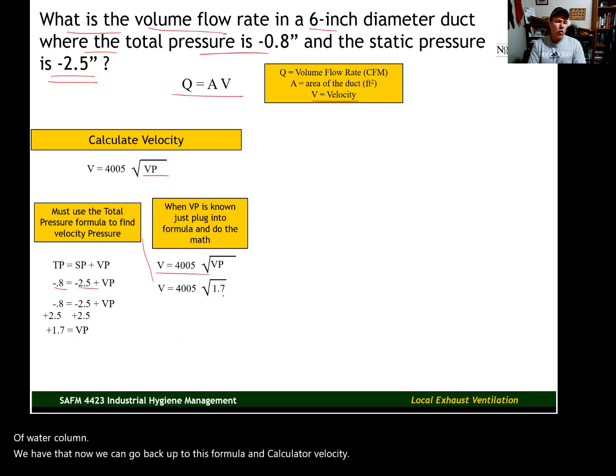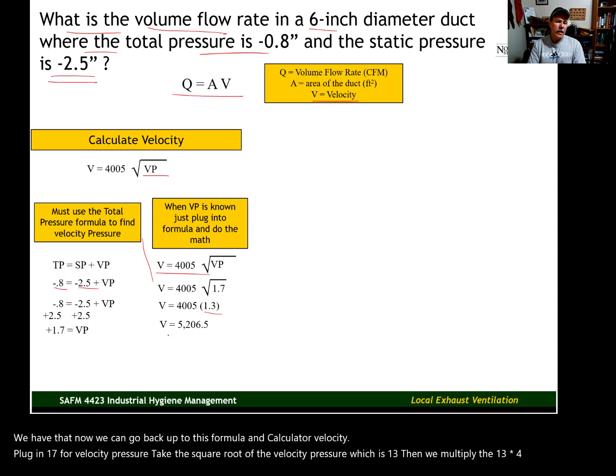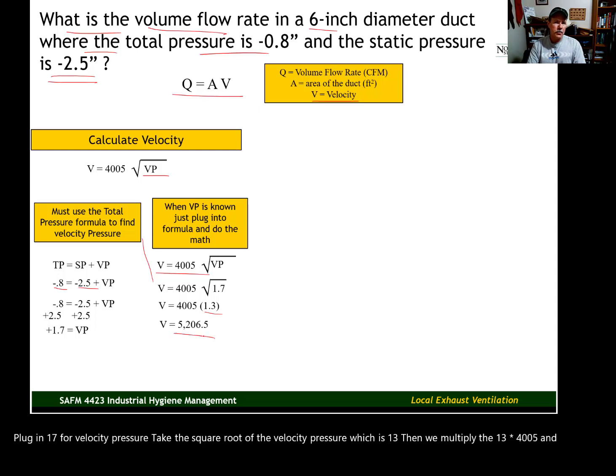Plug in 1.7 for our velocity pressure. Take the square root of the velocity pressure, which is 1.3. Then we multiply the 1.3 times 4005. And there's our velocity, 5206.5. Now we have the velocity that we need to calculate the flow rate.